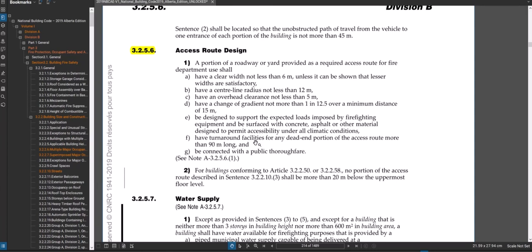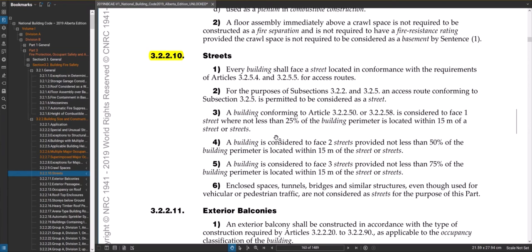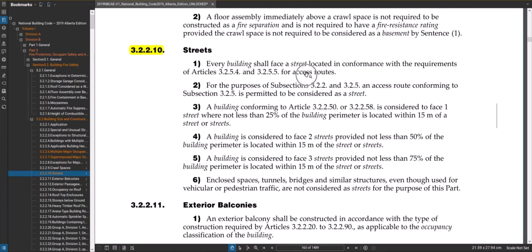Typically you have to show the access route on the site plan and prove you're meeting these requirements using a truck turning program or by indicating the truck can get around obstacles. There is also a possibility of a truck entering a site and having a dead end — it can back out, but the dead-end path can't be more than 90 meters long. If the path to the principal entry is more than 90 meters from the street, you'd have to provide a turnaround. So to summarize: determine how many streets your building faces, consider access routes as streets for section 3.2.2, and these are the four key elements needed to classify your building and find its construction requirements.